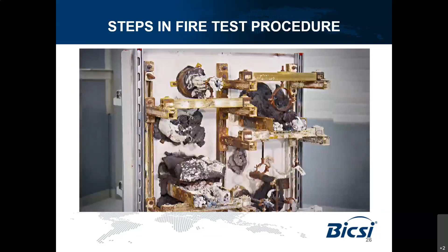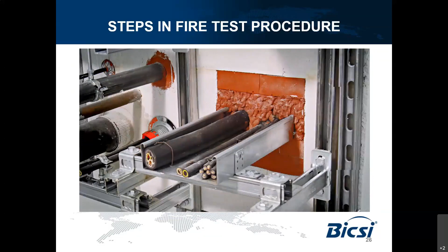As you can see, this is why we need intumescent type material - it expands, forming a foam char, a carbon char, to prevent heat from passing through. As you can see with this pipe ring, initially there's a pipe, but after the burn the pipe is totally gone, and it becomes a lot of intumescent material blocking the opening.